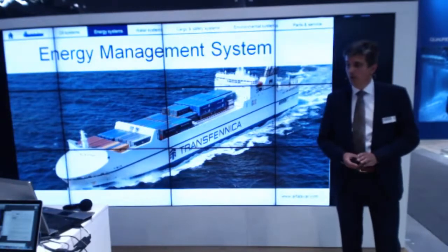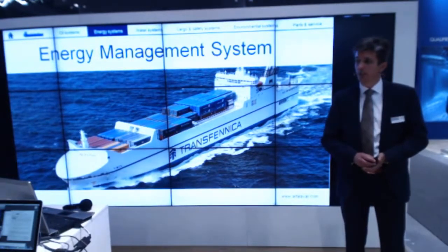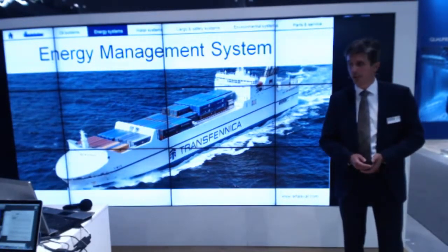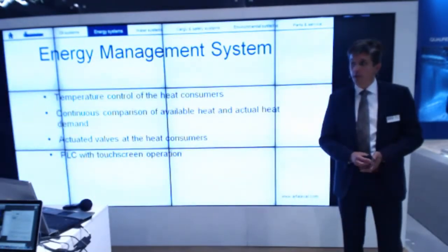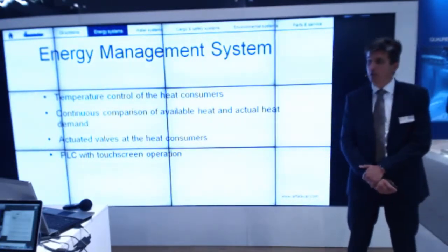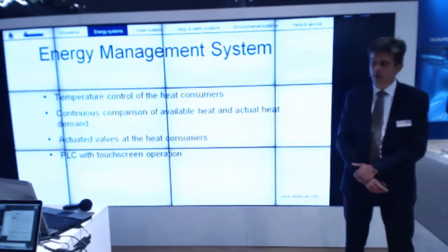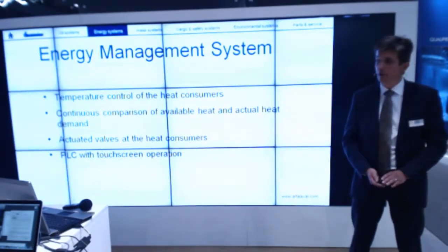In addition to a standard system where in most cases all the heat consumers are controlled by manually operated valves, we have an additional system called Energy Management System, or short EMS, where each and every heat consumer on board can be controlled from the control panel instead of manually operated. The Energy Management System is a temperature control system for the heat consumers and makes a continuous comparison between the available heat from the heat sources and actual heat demand from the various consumers. It's done by actuated valves at the heat consumers and by means of a PLC built into the control panel with a touch screen for operation by the crew.